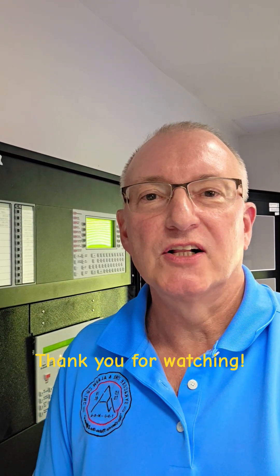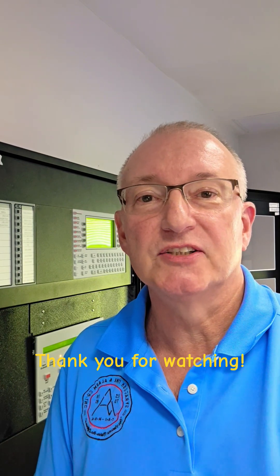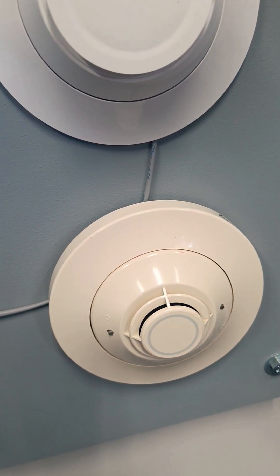I would like to thank one of our viewers for their comment regarding flash scan and clip mode, and how sometimes they seem like they might be interchangeable. This is our 320 system, which is currently set to clip mode. There are two bright white sensors on the SLC, along with an older ivory sensor below.